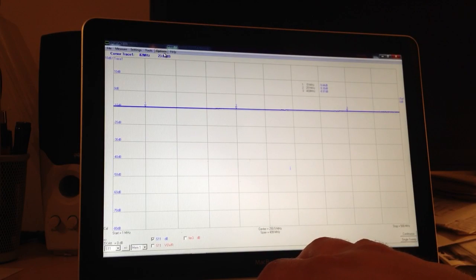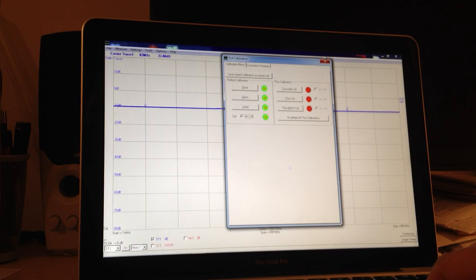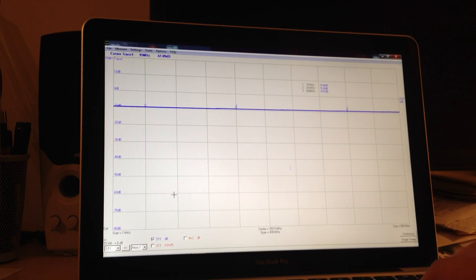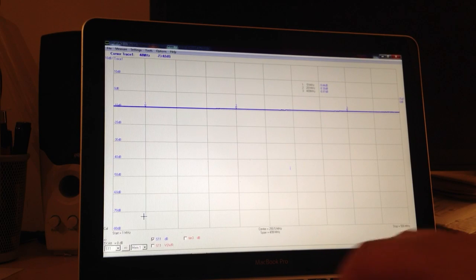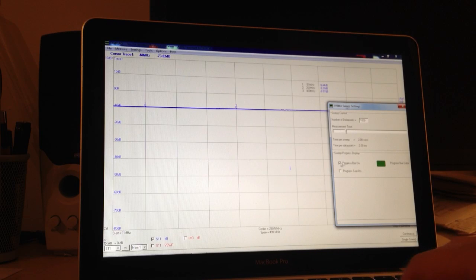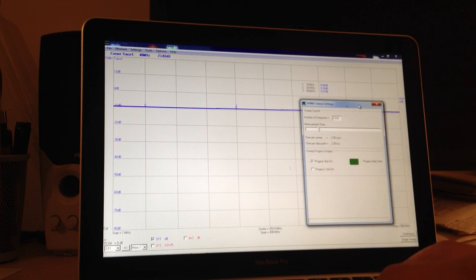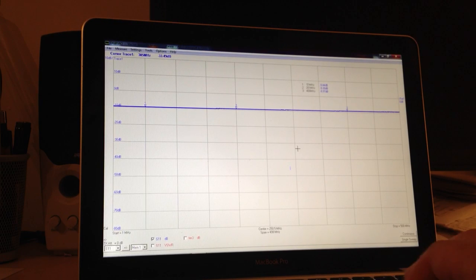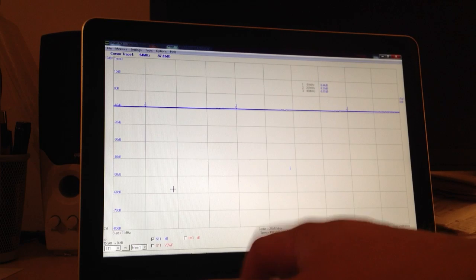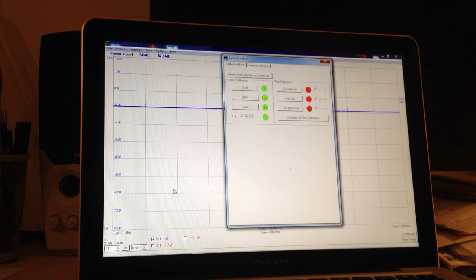On the software side, I have set up the frequency range from 1 to 500 megahertz, 1000 samples, 2 milliseconds per data point, resulting in 2 seconds of total sweep. So let's start with the calibration. I'm going to connect open first.